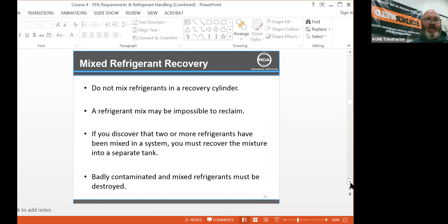Mixed refrigerant. Do not mix refrigerants in a recovery cylinder. A refrigerant mix may be impossible to reclaim. Mixed refrigerants are destroyed. They can't reclaim them. If you discover that 2 or more refrigerants have been mixed in the system, you must recover the mixture into a separate tank. We don't do that here. We actually label the bottle as mixed gas, and we let rapid recovery take care of it.